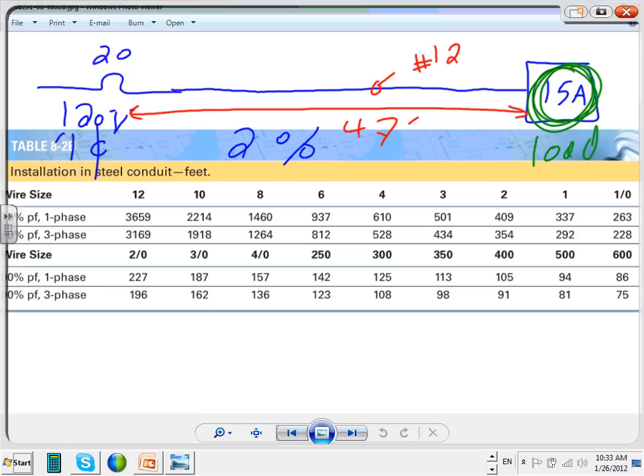Any questions about this, how to use this table? We'll be using more of this next quarter. That's not a whole lot. Now, can I apply this rule to the lights in my room? No, mistake number one. Here's a branch circuit, and I add all the amps for the fixtures, and I came up with 16 amps. And oops, Chad, I violated 47.